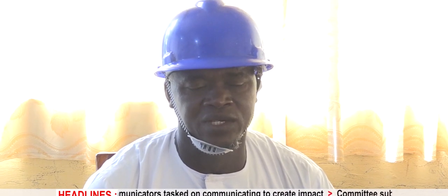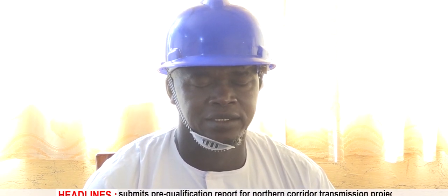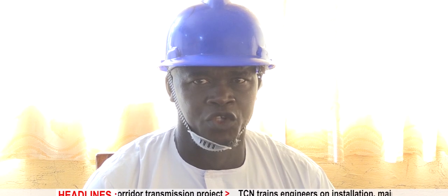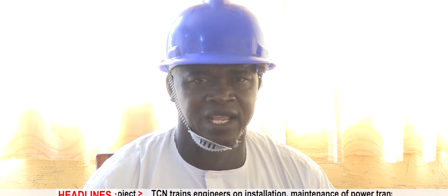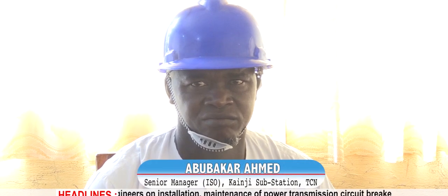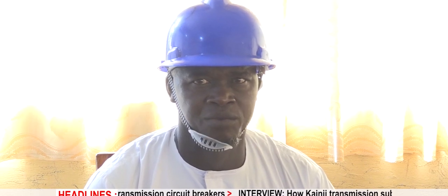Presently we have two radiating outgoing feeders, feeder 1 and feeder 6. Feeder 1 feeds the injection station closer to the station, which is New Busa. That injection station has one 7.5 MVA transformer, and it has three outgoing 11kV feeders: Township, Senior Camp, and Nasarawa.